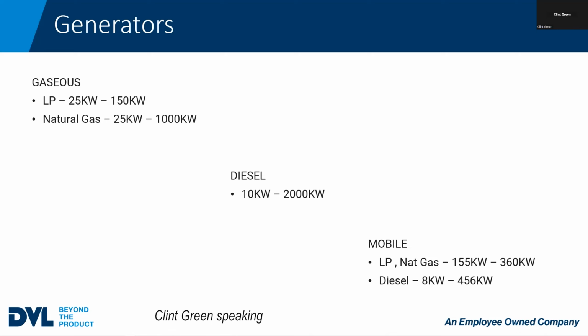What type of enclosures do you want? These are all different things that we need to look into. How many circuit breakers do you want to isolate your loads? Do you want to break up the different areas of your building? Maybe you want to back up life safety, critical, and just a set of equipment, and put priorities on what takes priority on starting, based on the size of the load coming out of the generator that's available.